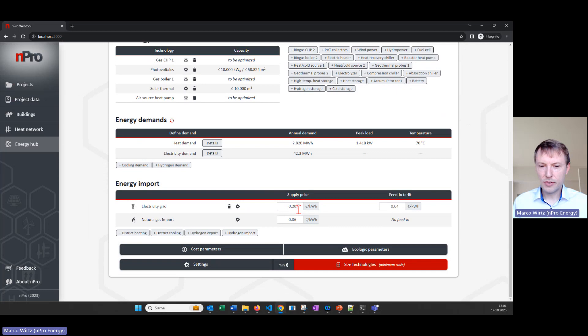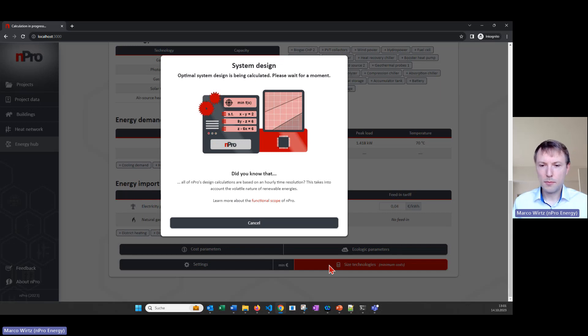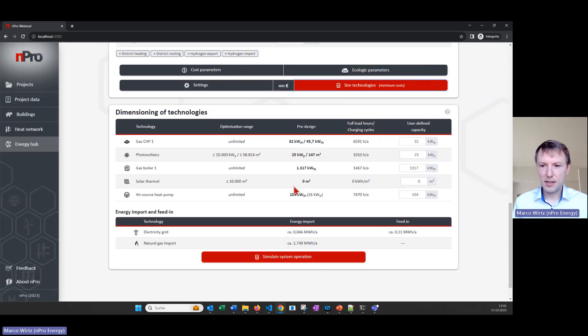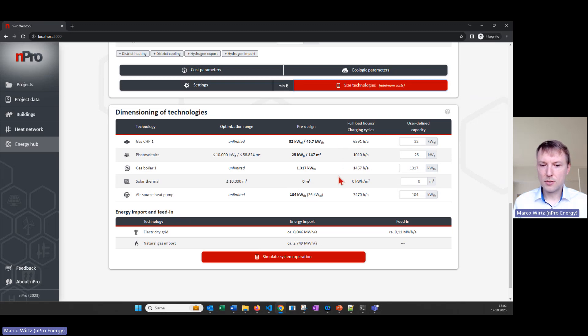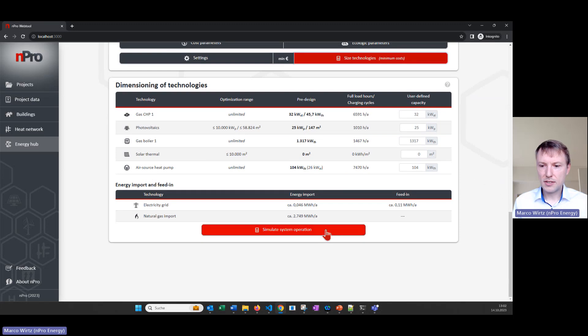We have to define the investment costs as well as the electricity prices, because they influence the optimization. Then I click on 'Size Technologies' and the program will calculate what the optimal configuration of the technologies is. In this case we see that the solar thermal is not used at all — it's not part of the cost-optimal system. We have the gas boiler here for the peak load, a small heat pump which covers the base load, and also the CHP covering some base load.